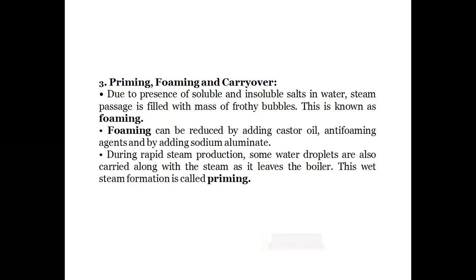During rapid steam formation, some water droplets are also carried along with the steam as it leaves the boiler. This wet steam formation is called priming. Means when a large amount of steam is produced at a certain time, some of the water droplets are carried with the steam. This process is called priming. Priming is also called carryover. Carryover is caused by impurities in the water, a high water level, and the method of operation of the boiler.